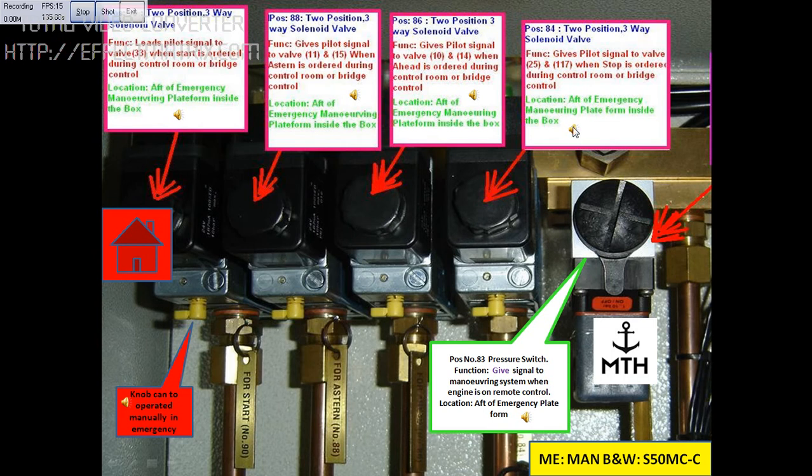This block is position number 84, which is a two position three-way solenoid valve. The function of this valve is to give a pilot signal to valve number 25 and 117 when stop is ordered either from control room or from bridge control.